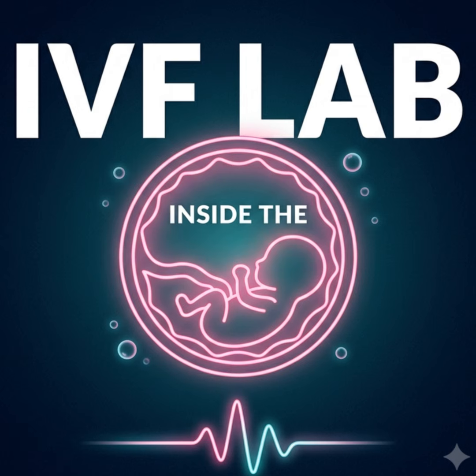So the solution borrowed heavily from aerospace and advanced optoelectronics. Indium tin oxide, or ITO. Indium tin oxide. Yes. The embryologist doesn't place the petri dish on cold metal. The inverted microscope features specialized, optically clear glass insert plates that sit directly above the objective lenses. Wait, but standard glass is an insulator, not a heating element. Which is why these specific glass plates undergo a highly specialized vacuum deposition process. They are coated with a microscopic, atomically thin layer of indium tin oxide.